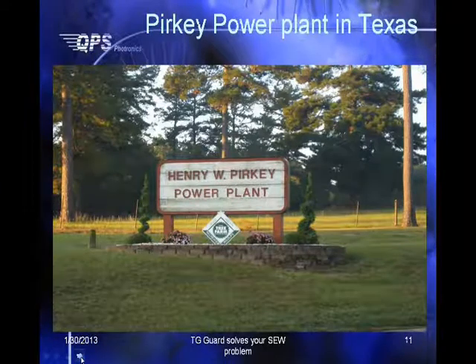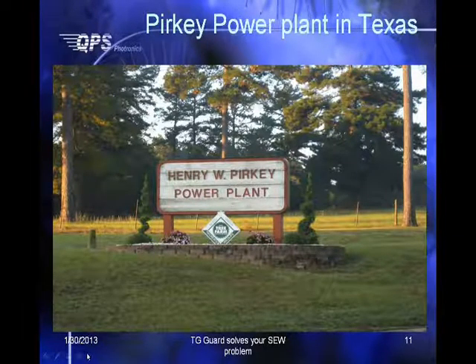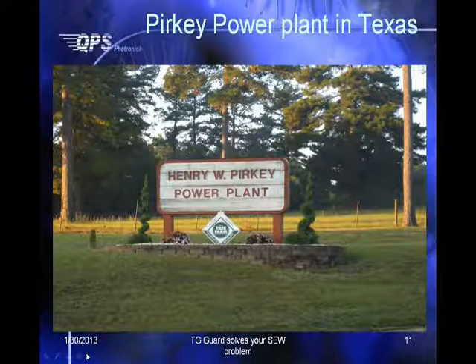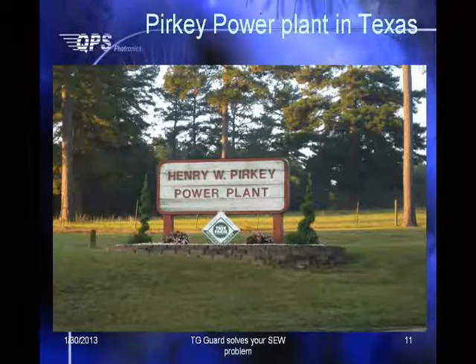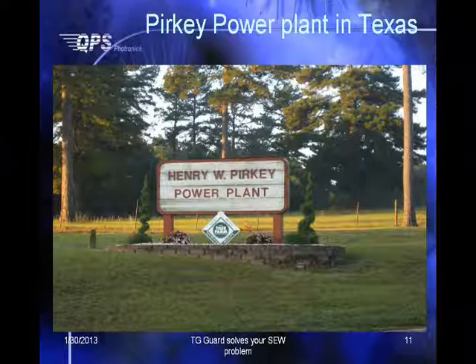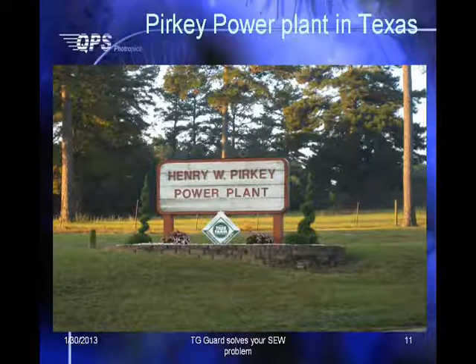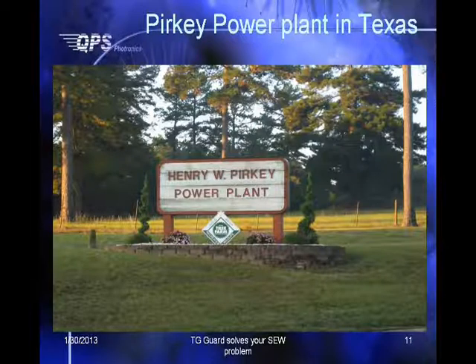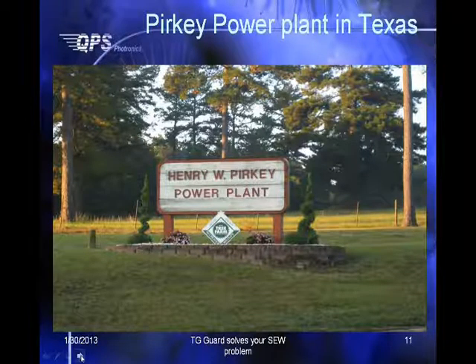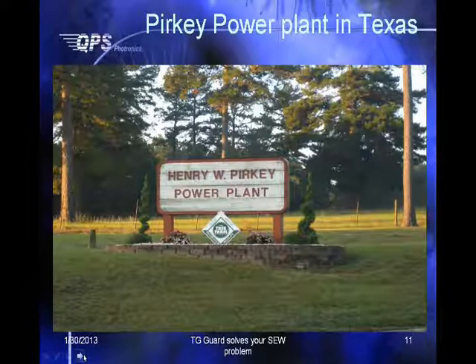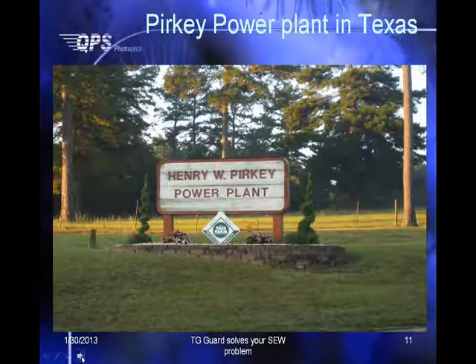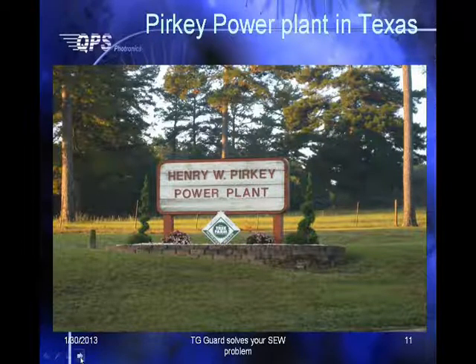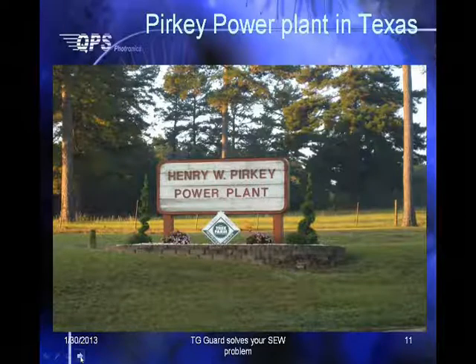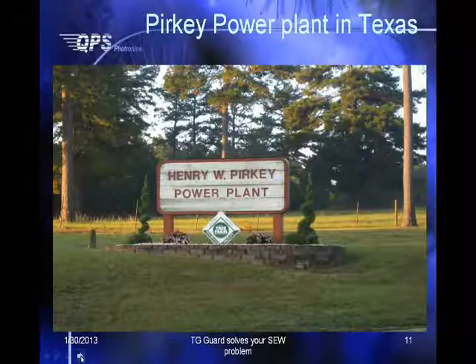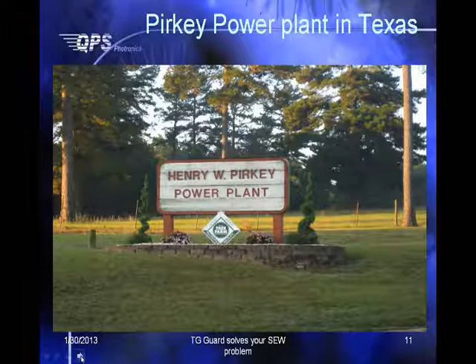I think in the industry there is still some controversy. For example, some engineers will say the vibration in the generator is mechanical in nature. It starts with imbalance, and the whole frame of the stator is vibrating. If we think about that concept, then the vibration frequency of such a signal should be one-time line frequency, because if the whole stator is rocking, it should be aligned with the rotation rate of the rotor.